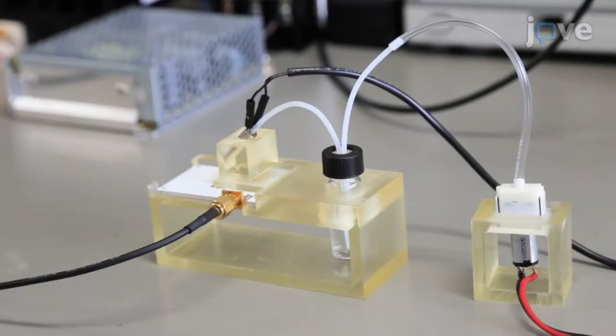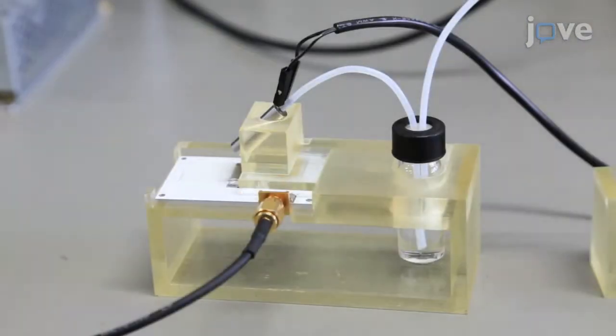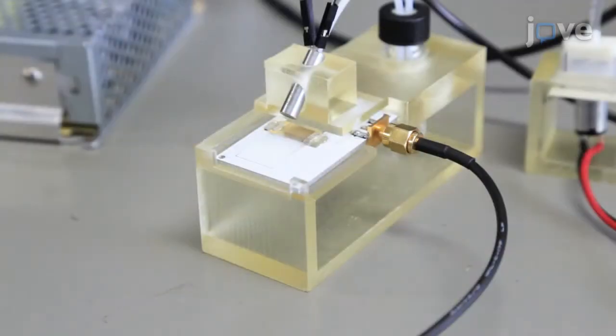Air will enter the vial through the action of the micro air pump. The fluid from the vial will go to the solenoid valve. The valve is set up to dispense liquid on the atomization area of the device.